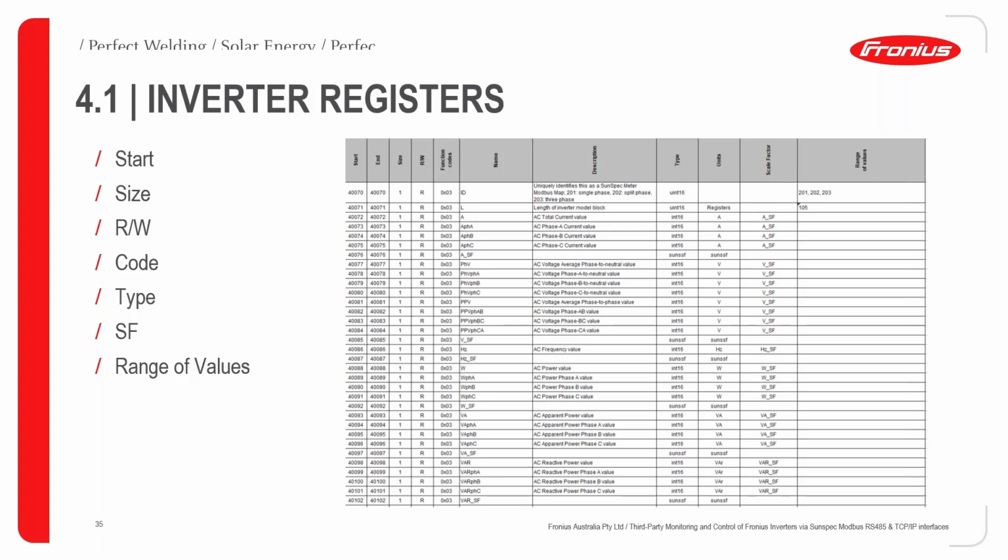Reading and writing registers. The supported function codes, as shared previously, are 3, 6, or 10. What's the name of the register? Some description there. I would point out the register type to the inverter. This will tell you what values you can expect there, if it's unsigned integer 16 or 32, and the scale factors that will bring you to the name of the register used for the scaling factor you need.